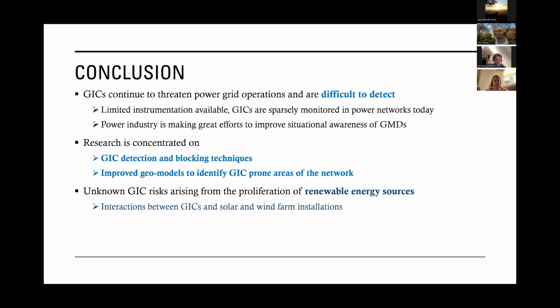Are there any grids that might be particularly vulnerable to GICs, considering the age or configuration of the grid, and also the ground it covers? Mainly in the polar regions, and long transmission lines there have, as the Quebec scenario showed, been most vulnerable, because the higher the voltage, the longer the lines, and longer lines are the most vulnerable. But we can't avoid that; we need long transmission lines to carry energy where it's needed.